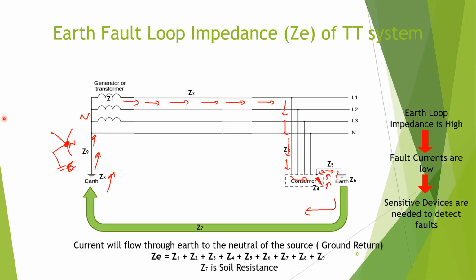So I said someone is the fault impedance. No, that is the impedance through earth. Earth loop impedance is the total loop impedance. So earth loop impedance, see, Ze is the earth loop impedance. So Z1, Z2, Z3, the addition of all those things will be earth loop impedance.